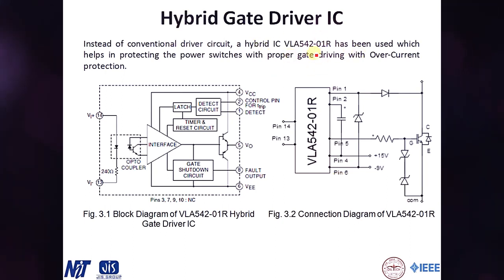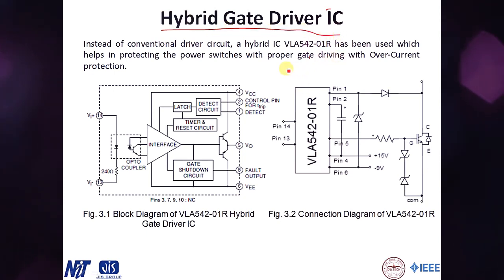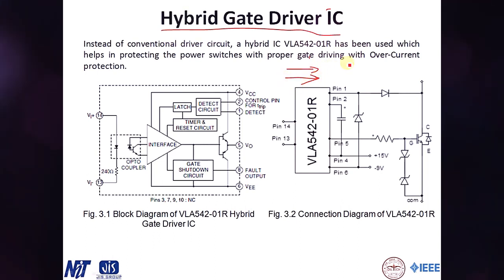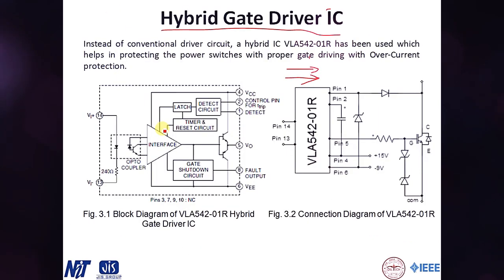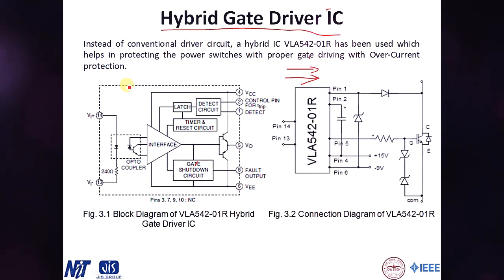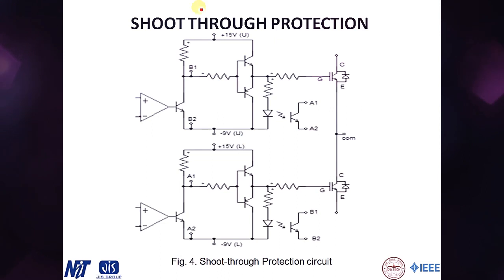For implementation, we use the VLA542-01R hybrid gate driver IC. This IC handles both proper gate driving of the IGBT and the overcurrent protection scheme described — the entire overcurrent protection logic is built inside this hybrid gate driver IC.